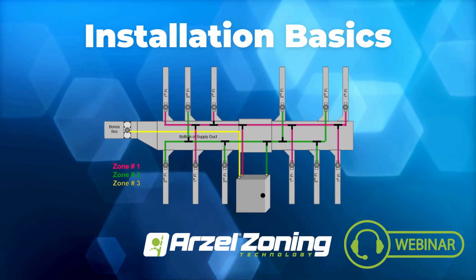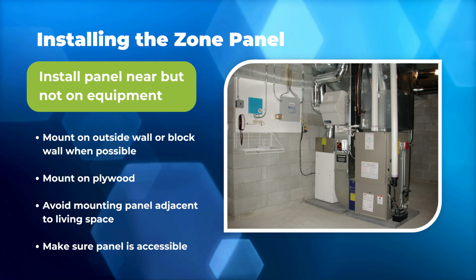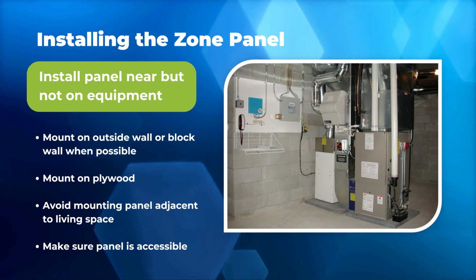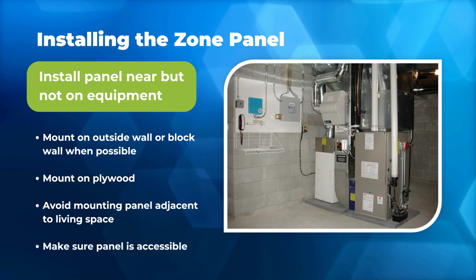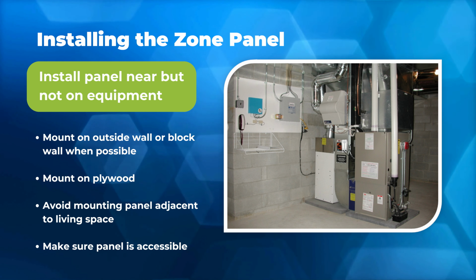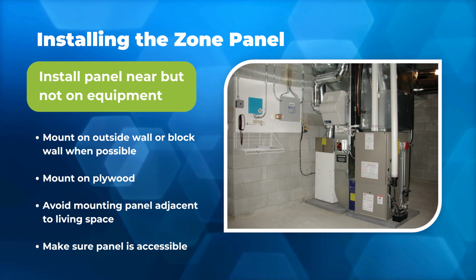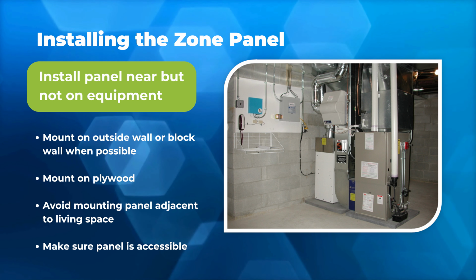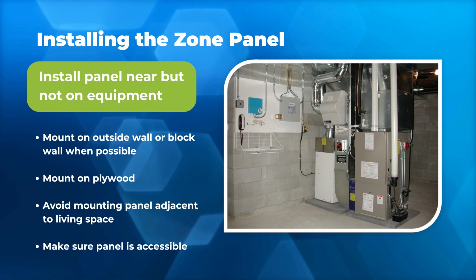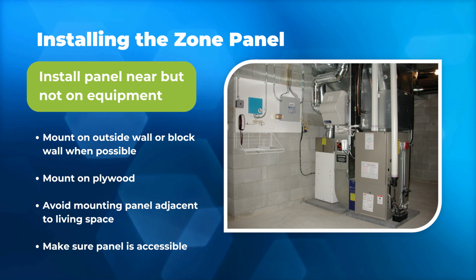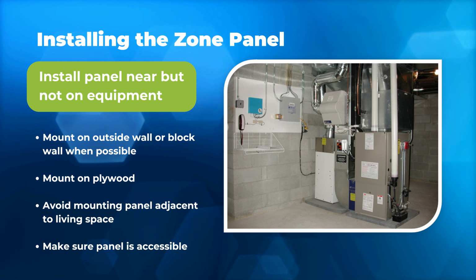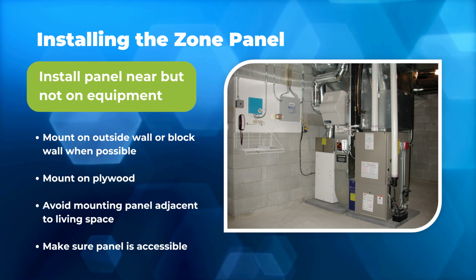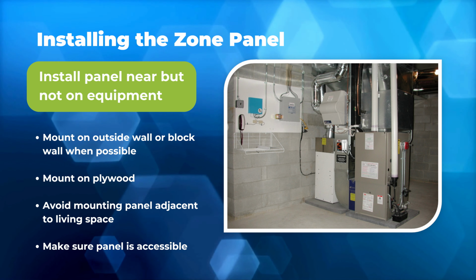So the first thing with installing any of our products is going to be where to mount the panel itself. With our system, the only sense of noise on the whole system is going to be the panel box itself. And that's due to the pump being inside the panel because all of our dampers are pneumatically driven. So to get those dampers to open and close, we have a pump built into the bottom of each of our panels, and that is the only sense of noise. So you're going to want to keep that in mind when you're installing the panel itself.